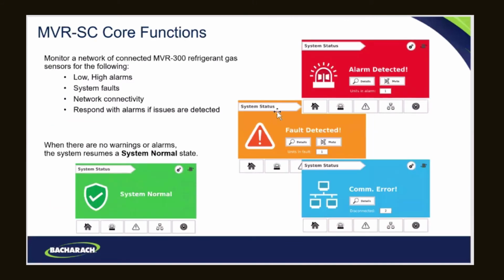This is just a slide that shows the different screens. Again, system normal. This is what it's going to look like if there's an alarm detected. It'll give you the ability from the controller to mute the alarm, so that will mute it in the room. You have the ability to go in and click on the details, and then it will bring up that particular room, and you can see if it's a low alarm, a high alarm, etc.